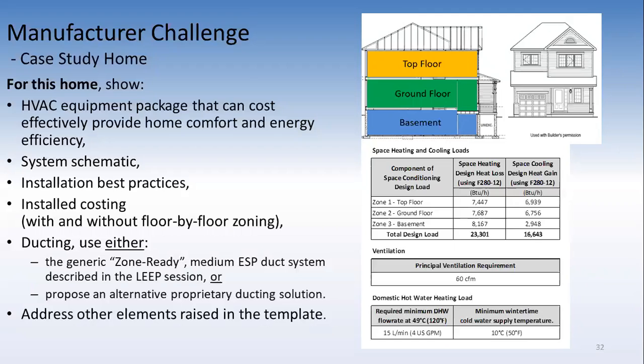I'm speaking a little bit from a Canadian perspective, where we are dealing with very energy efficient conscious builders. One of these, there's an example on the sheet that you're looking at right now. We've been a part of a program traveling across Canada, putting on our equipment selections and showing builders across the country what can be done in these situations. And I'm happy to share that with you right now. So taking a look at the design load for this specific home, 23,000 BTUs of heating and 16,000, 1.4 tons of cooling requirement on this 3-story home.